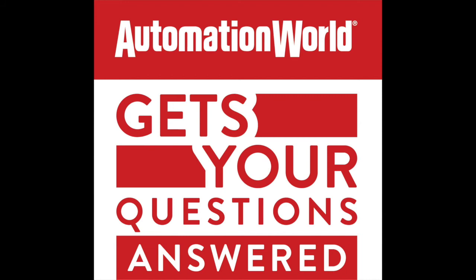That's a great question. It's very important to understand what type of housing you need to put around the sensor elements in order to survive the environment. And one of the things I really like about the global and the North American rules, like the North American NEMA or the global EN 60529 or the IEC 529 ingress protection, a lot of people call them the IP codes, is that these ratings come in really handy when you're asking these types of questions because they rate the sensor body's ability to survive a particular environment.